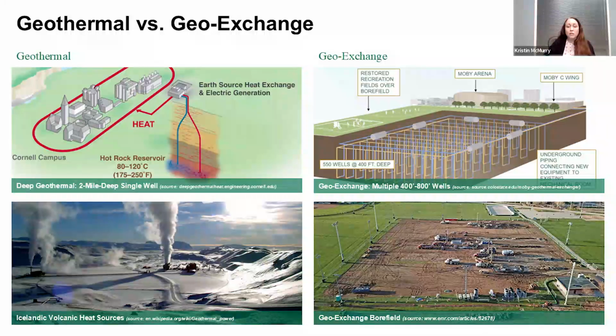Those are dug into a bore field, and the big thing you need to take away is that you need to balance your heating and cooling loads, because this is a storage system. Whatever heat you reject to the ground in the summertime is what you have available for heat in the winter time. You don't have more than that available.